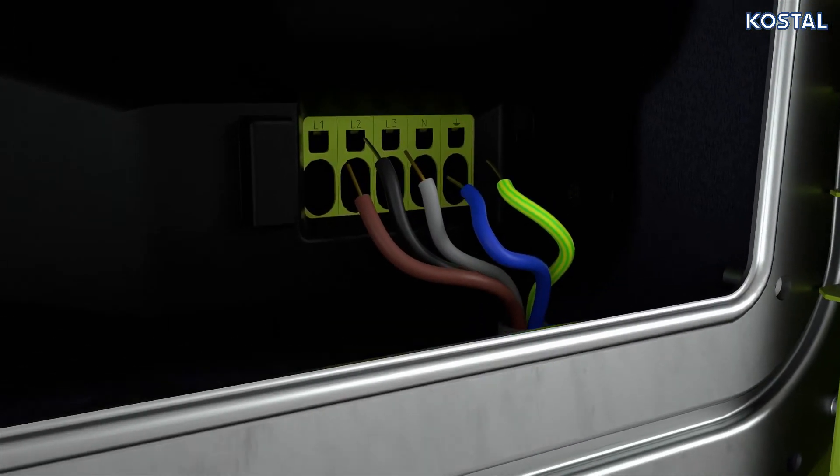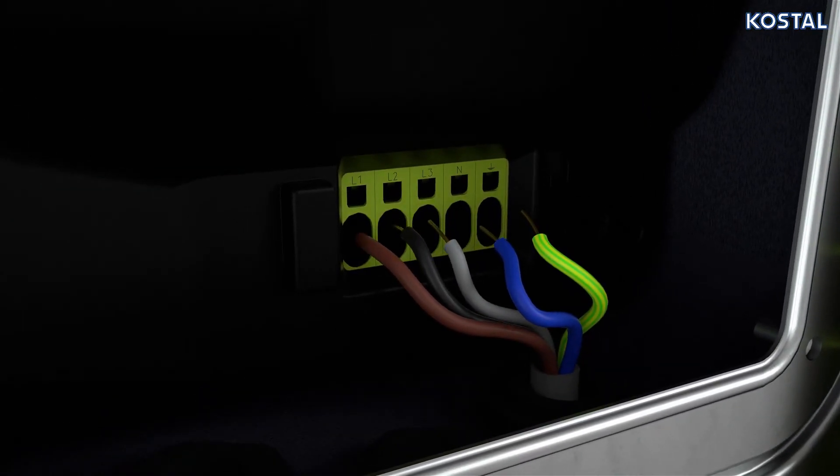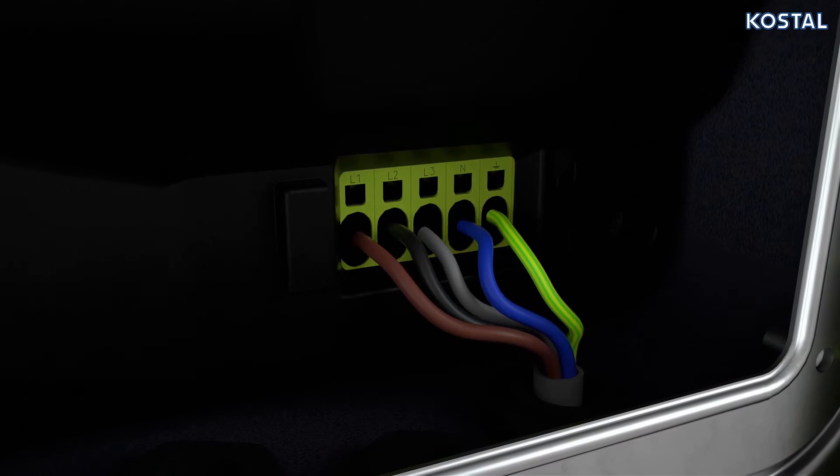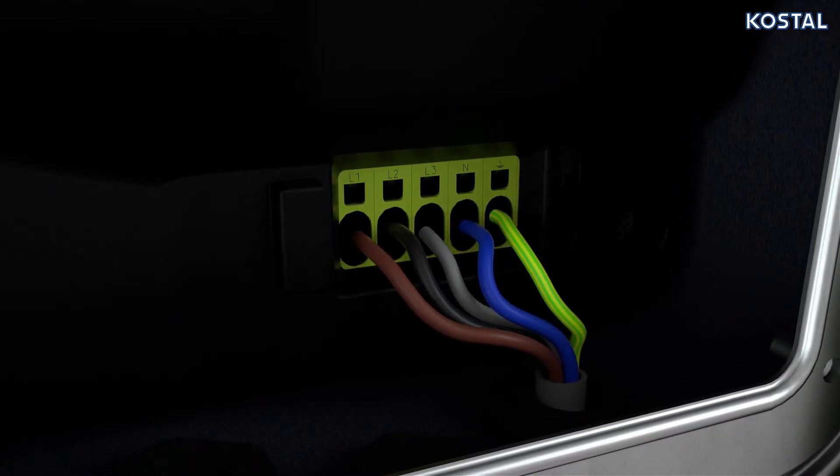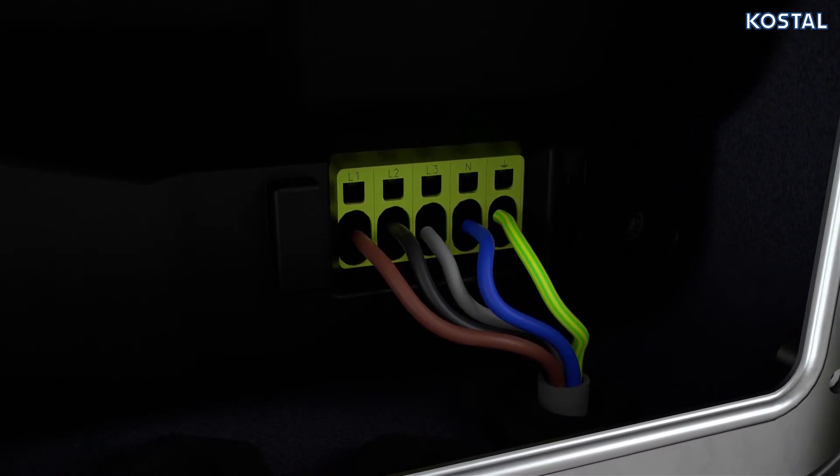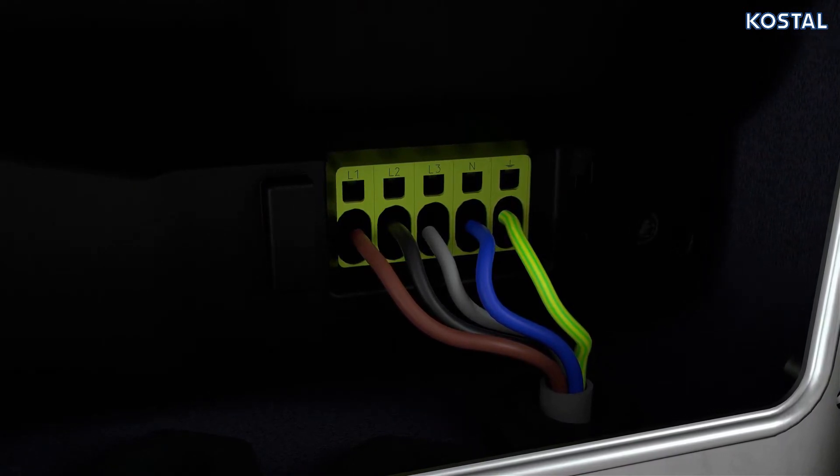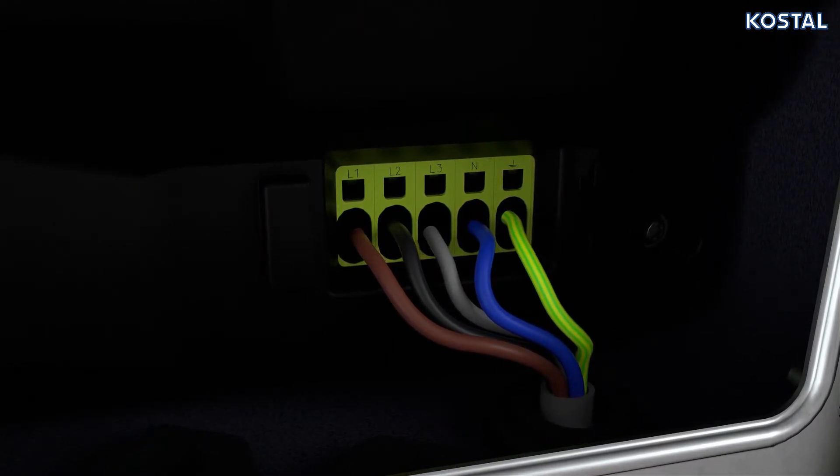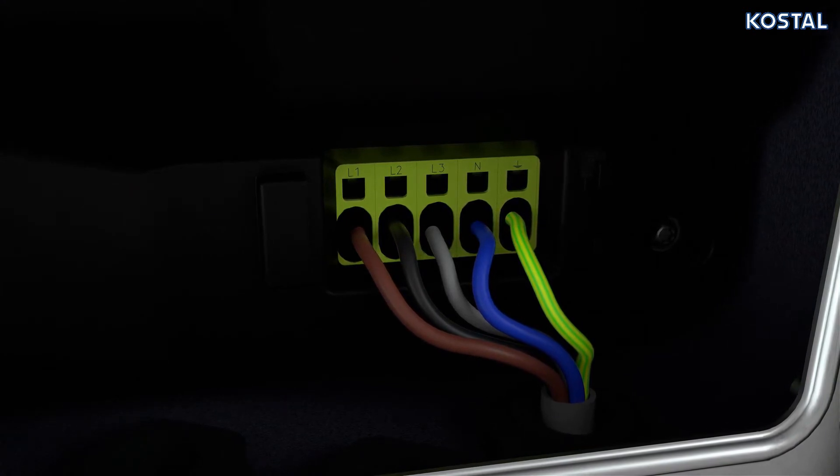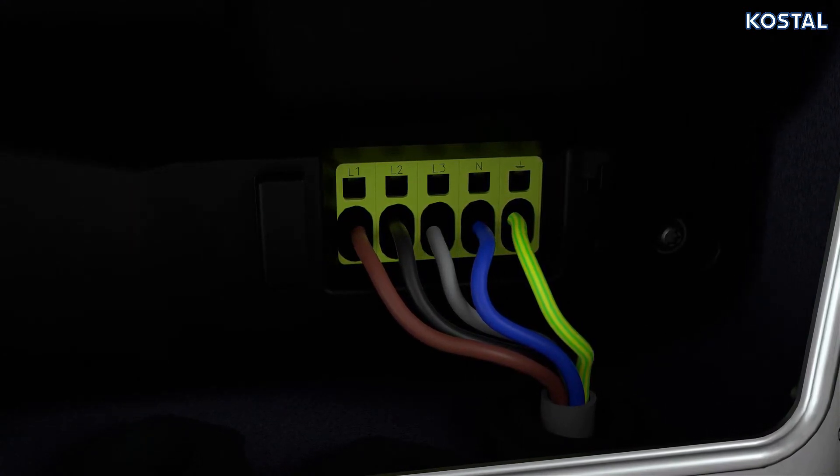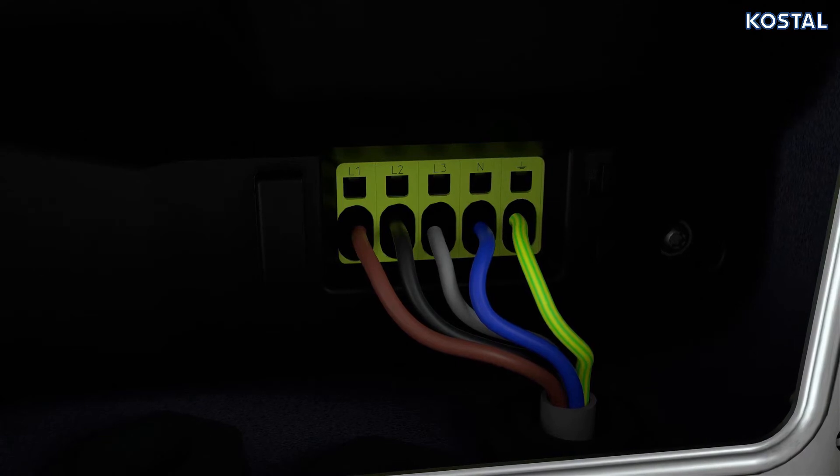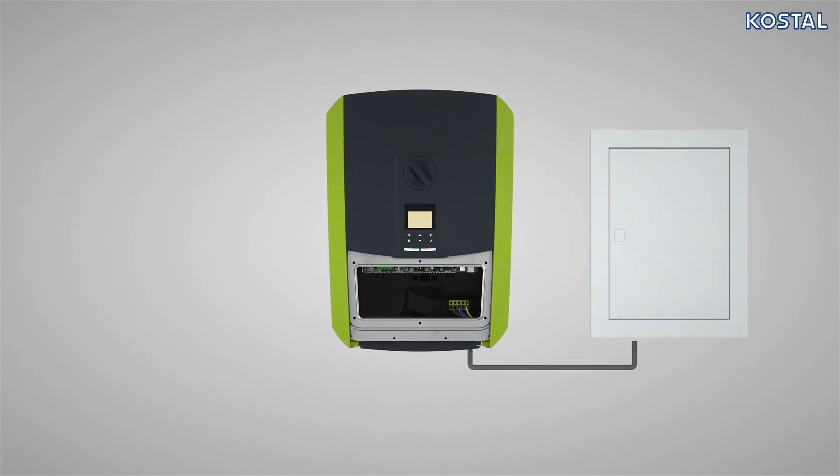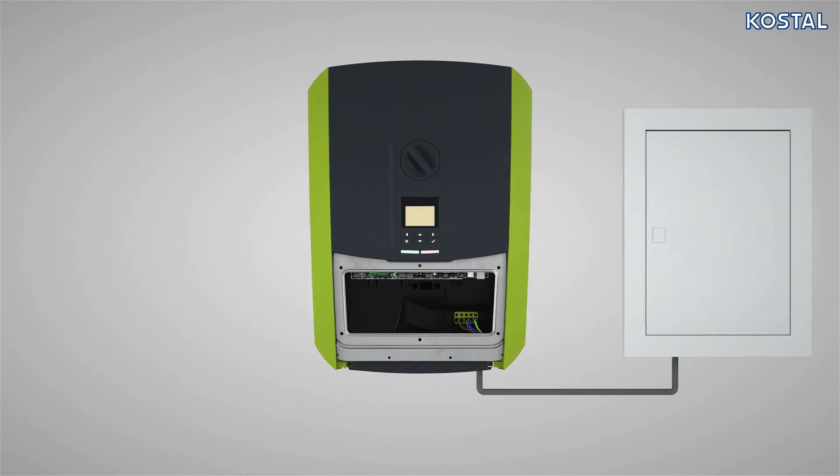Connect the wires of the mains cable to the AC terminal in accordance with the labeling. Insert the individual wires into the large, round aperture on the AC terminal. When using cables with fine wires, core end sleeves should be used. Ensure that there is a contact surface of 18 millimeters. The AC cable is now connected.